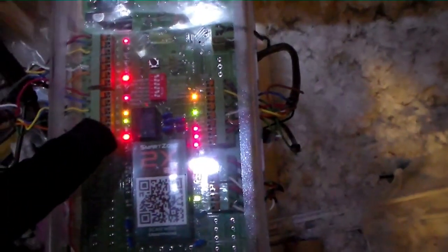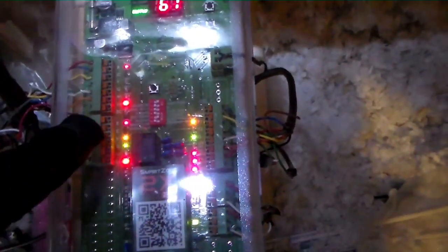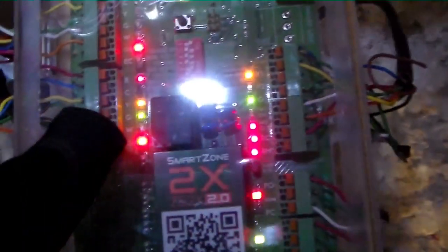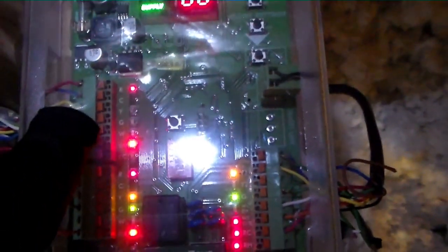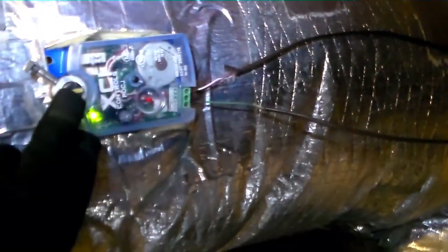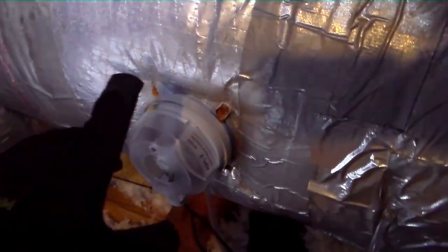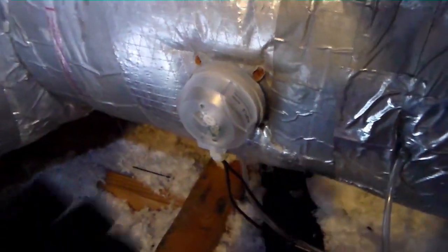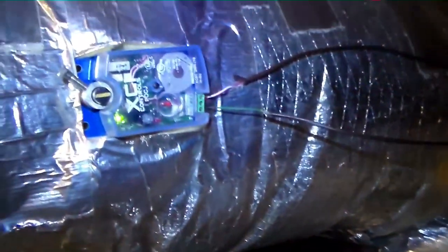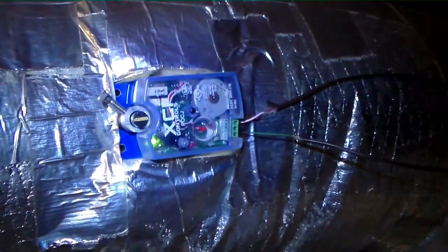As you see, guys, we're climbing down low really quickly, and if you look here, one zone is calling. That's why we have our reversing valve light, fan light, compressor light right there, all aptly colored. We go up here to zone 1, it's not calling yet, so it's going to get a very big temperature spread because we're recycling air through the bypass duct. It's all the way open. There's our static pressure switch. It's telling it that the static pressure is high and it needs to recycle air, and that's what it's doing. So we need to open up the larger zone, the main floor. Both zones are calling now, guys, so you see the bypass is shut because the static is in normal range.